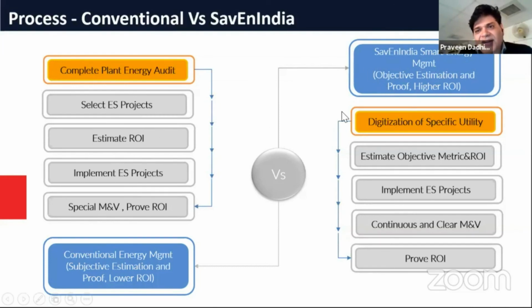Now with smart energy management, as SavEnIndia, what we do is digitize a specific utility. So let's say if you have a compressor, we install measurement devices on it: an energy meter to measure input, and an airflow meter and pressure sensor to measure output. Once you have the data, you baseline it, run analytics and energy engineering on it to come up with a solution, implement it objectively, and measurement also becomes very objective.